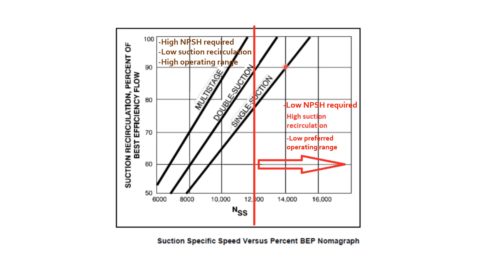At this point, the operating allowable range shall be around 90 percent of the best efficiency point. You have only this narrow window where you can operate your pump with best efficiency.